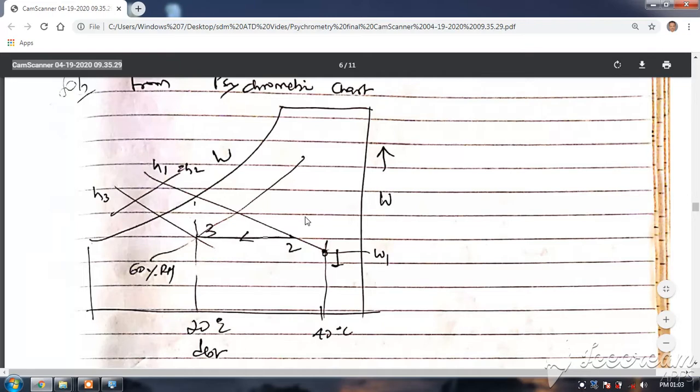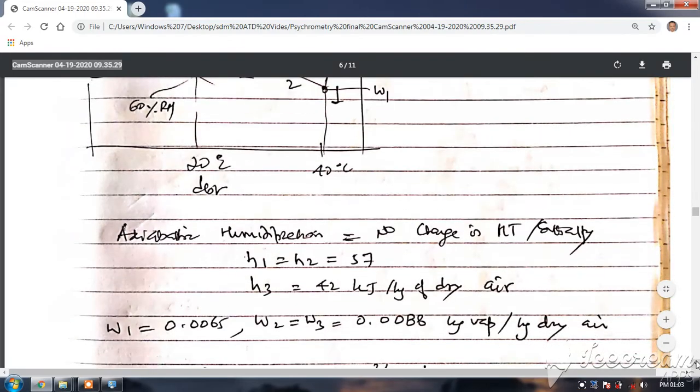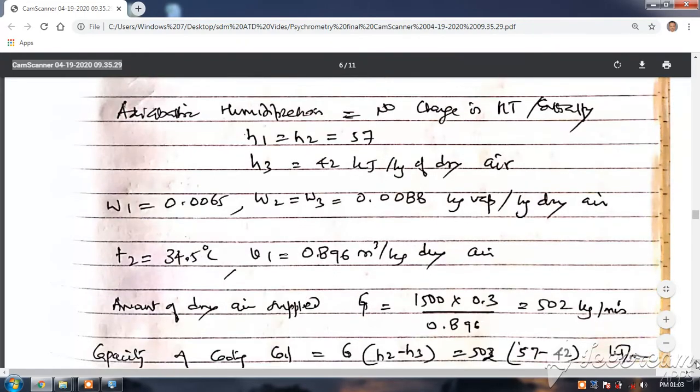Now enthalpy you can find out. Enthalpy of 1-2: h1 is equal to h2. This is adiabatic humidification. You can see adiabatic humidification which means there is no change in enthalpy. The enthalpy of 1-2, of 2 is 57, enthalpy of 3 is 42 kilojoules per kg.